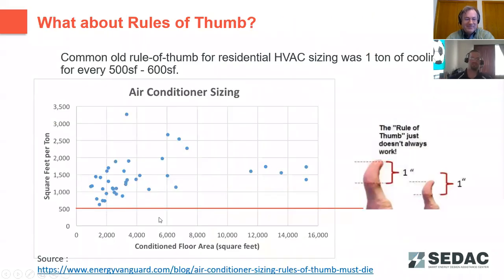More commonly, what we see is this rule of thumb for residential HVAC sizing, where 1 ton of cooling is required for every 500 to 600 square feet. However, with improvements in air tightness, insulation requirements, and things in the code, that rule of thumb rarely, if ever, applies anymore. And so now we say that rule of thumb just doesn't always work.